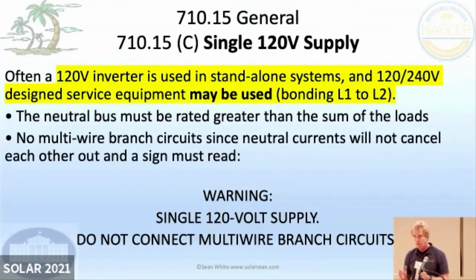So now if you got them both on the same, then they're not opposing each other. And so there's more current on the neutral. It's like double of whatever line one and line two is, or you add line one and two together. And so there's this rule that says you can't use multi-wire branch circuits. You've got to put a sticker that says that. A multi-wire branch circuit, some people know it as Romex, is one example of that, where you have a black, a red, a white wire, and then a ground. So it's 3 plus a ground. You can't use that when you're going to do a 120 volt inverter, and you'd have to put that label there.